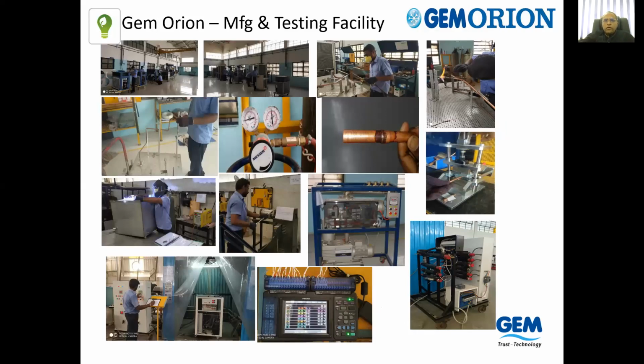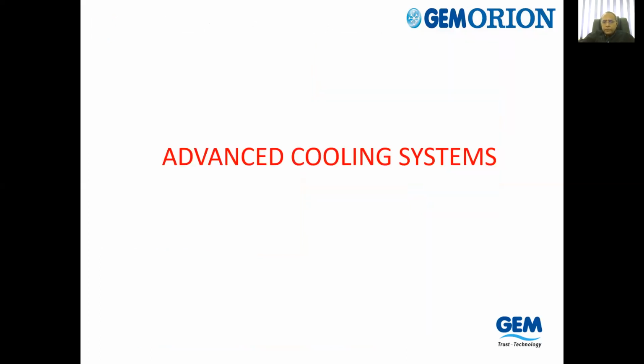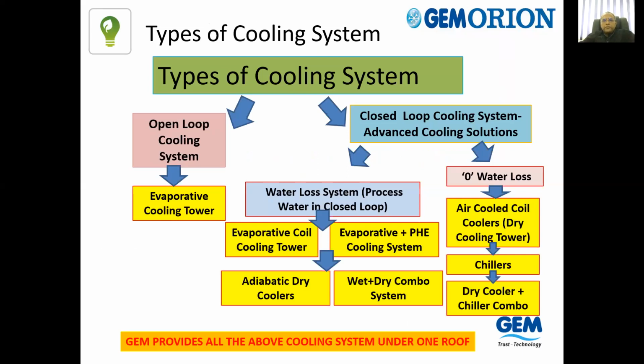So to give an overview of our process, our complete brazing process has been qualified as per Japanese standard. So now coming to the types of cooling systems, you can see my pointer. The open loop cooling system has got an evaporative cooling tower, which is what people have conventionally been using. Now, when we talk of saving water or saving the process from maintenance, then we have to look at closed loop cooling. And in closed loop cooling also, there are two methods.